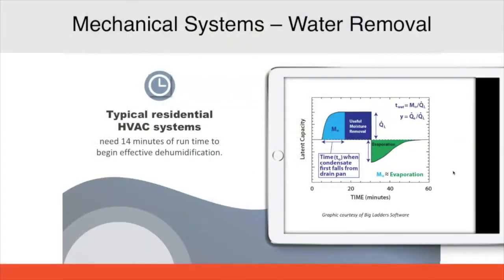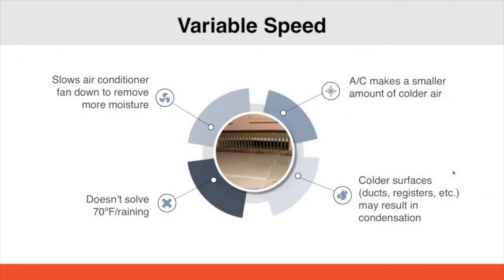So mechanical systems typically need about 15 to 20 minutes of effective runtime in order to really get water dripping down the drain. So we don't want to oversize our mechanicals. We want to make sure that we right size as much as possible to get longer run times in order to get that effective dehumidification from the systems. So variable speed slows the air conditioning down, we can remove more moisture, and this is what we talked about in the part one webinar, about really maximizing our air conditioners to remove as much moisture as possible without creating any issues.